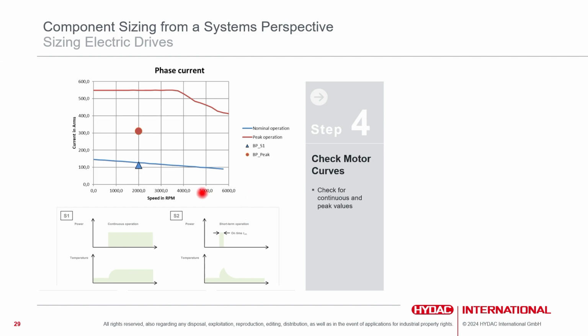The one is the continuous operating point, the blue one here. And when it comes to current, which is what ultimately determines the motor size, the operating point is below that continuous operation line. We also see that the peak current is quite a bit below the peak curve of the motor. So it seems quite good. It seems we have no problem, but we are also not heavily oversized, because the continuous operation is pretty close to that line.